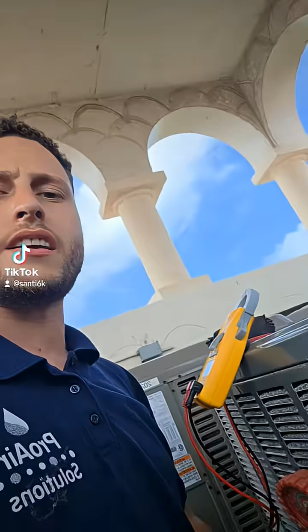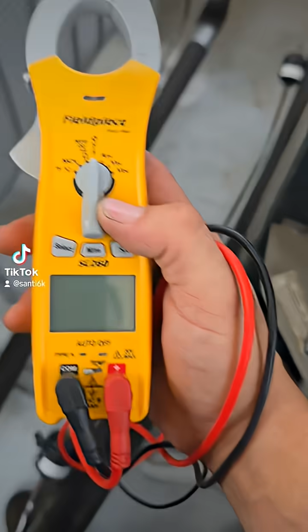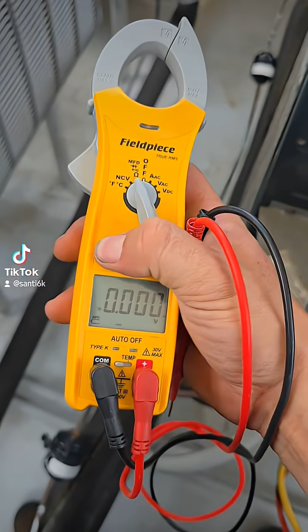Now, if you come out here and your fan is running, but it is not getting cold, if you listen closely, you won't hear that compressor. More than likely, you have a bad capacitor. So then we go ahead and take a test on that. You're going to set your meter to microfarads. There we go. We got that ready. And then we can go ahead and test it.